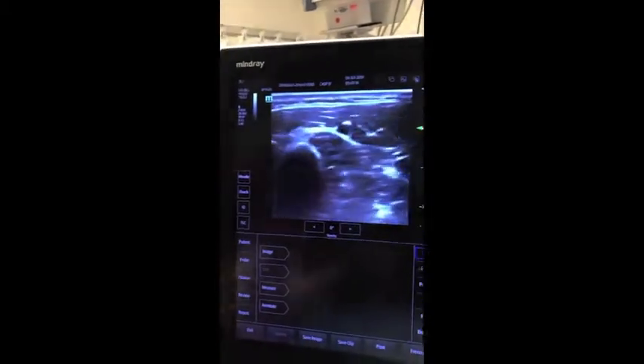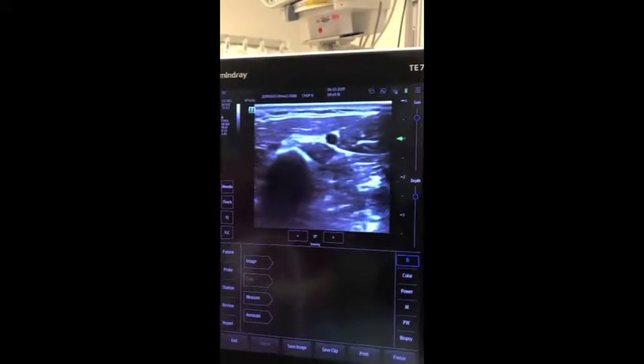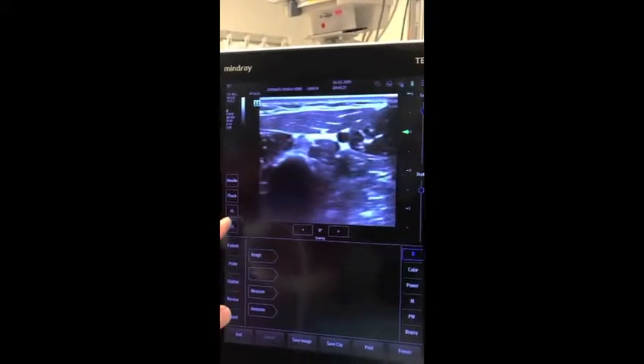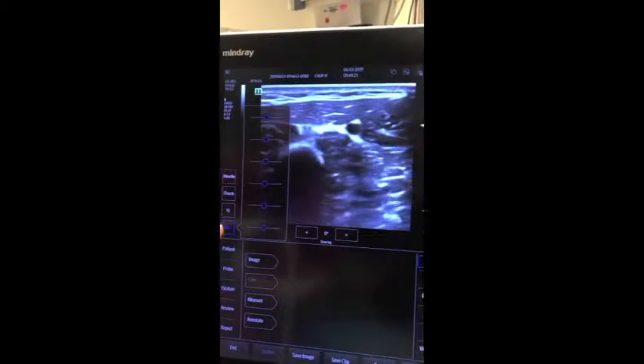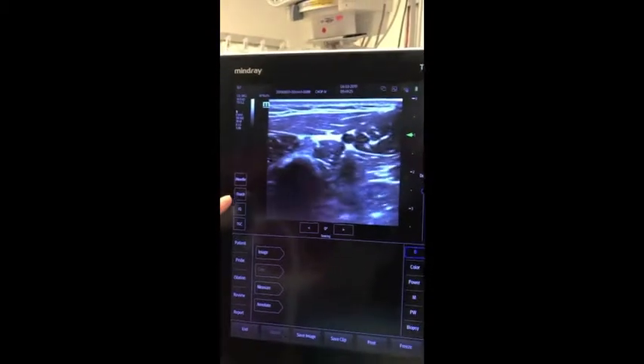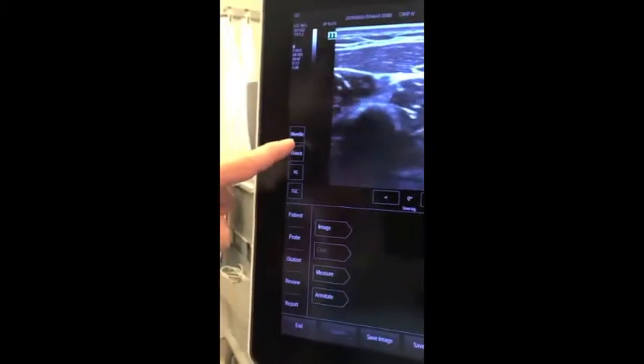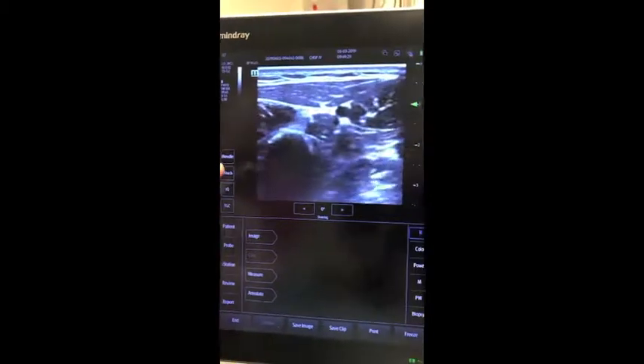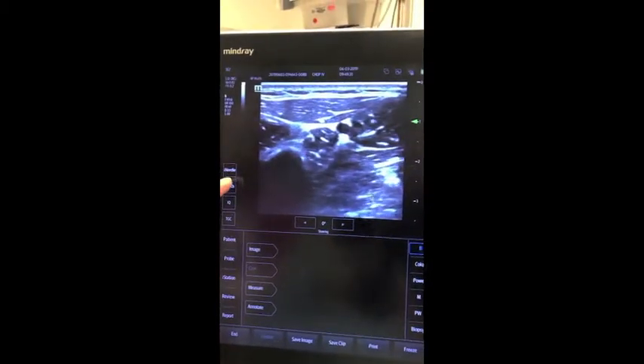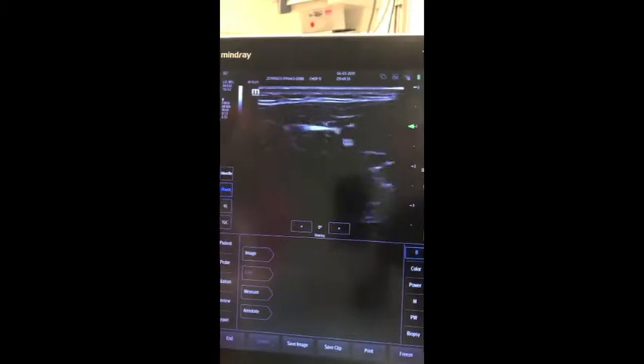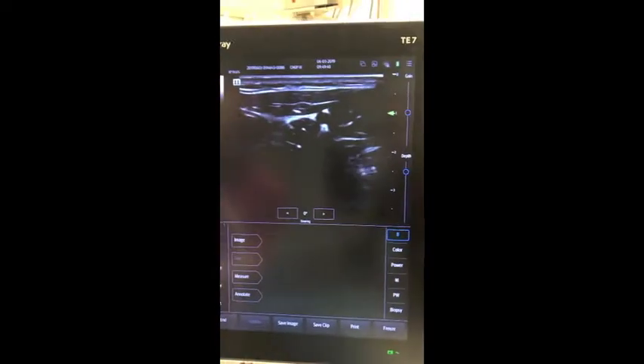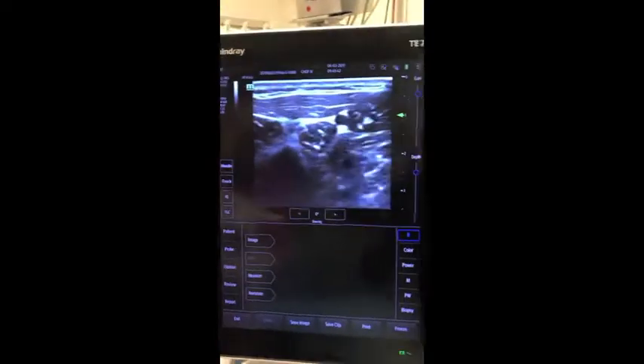All right. A few other things that you might need to adjust is TGC, which is here, which is the gain in different levels of the field. You can do the auto optimize button, which is this iTouch button. I would encourage not to do it. It's not great on this machine, but it does auto optimize what the machine thinks. You can see in here it's a little bit dark. One thing to remember is to get out of it, you actually have to press and hold it to get out of it.